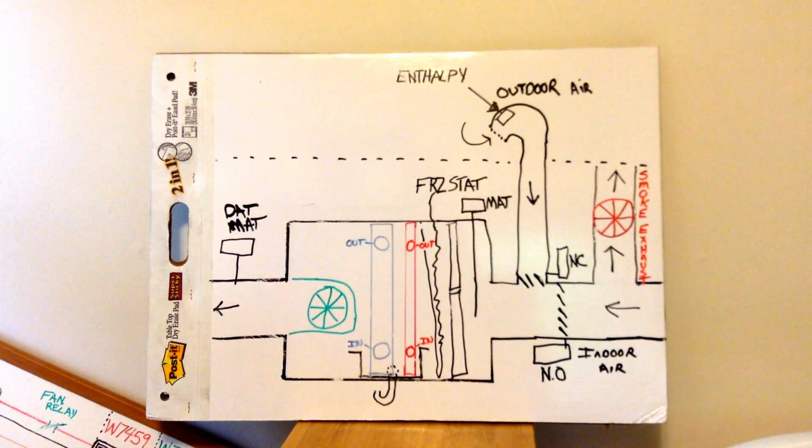the way. One thing I want to mention while I'm here is just basic positioning. You can see that this is the mixed air temperature sensor. These are the filters, or what I tried to draw as filters. So this is measuring the mixed air temp after the two dampers. Once we're mixed, we're trying to get to 55 degrees here, everyone. The freeze stat needs to go in front of the coils. I see guys that put it after the coils.